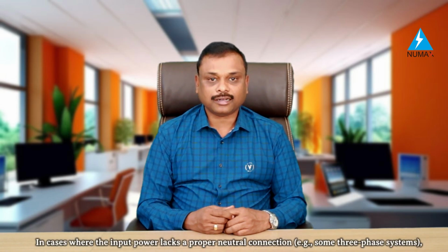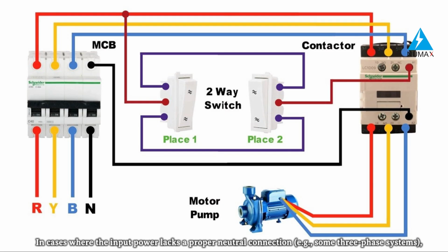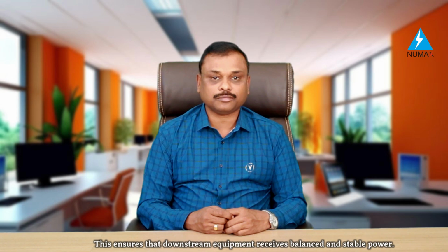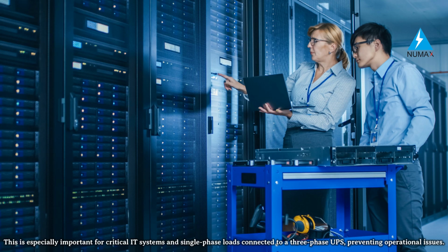In cases where the input power lacks a proper neutral connection, for example some three-phase systems, the isolation transformer creates a new neutral point on the output side. This ensures that downstream equipment receives balanced and stable power. Benefits: this is especially important for critical IT systems and single-phase loads connected to a three-phase UPS, preventing operational issues.